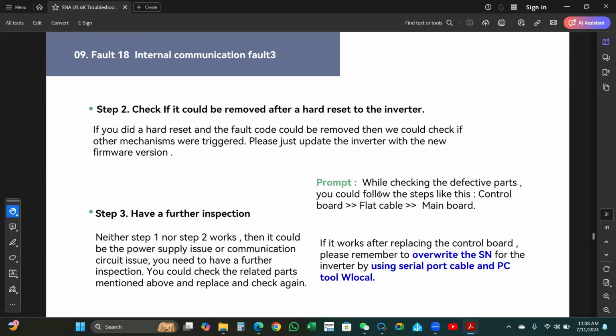Control board, flat cable, and main board. If it works after replacing the control board, please remember to overwrite the serial number for the inverter by using a serial port cable and PC tool WLocal.